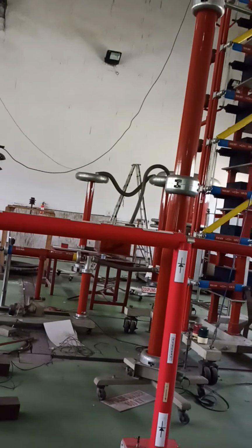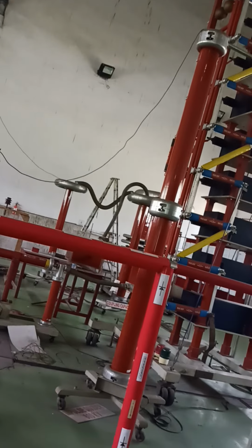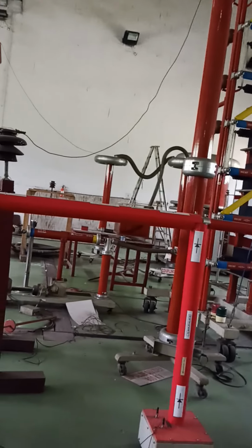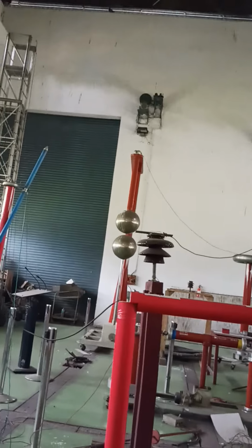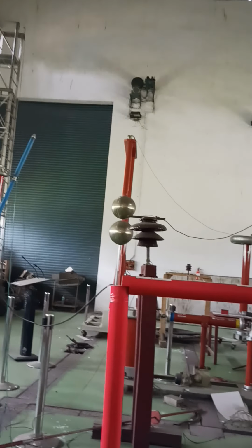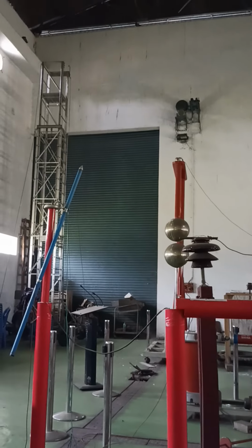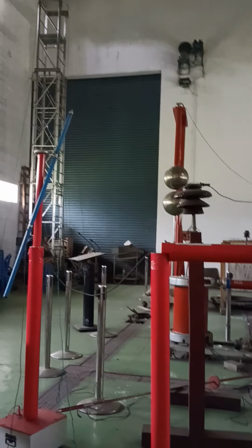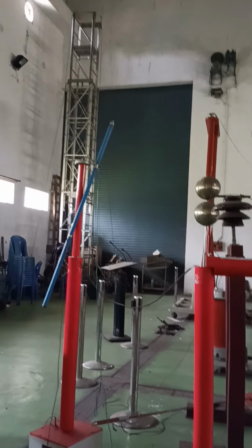Basically, we are applying the charges and testing how much insulation it has right now. The breakdown voltage we are testing. That means we apply a voltage there and check whether there is some charge discharge or not. It will be an 800 kV, 1.2 microsecond impulse. Oh, 1.25 microsecond. These are the characteristics of a normal thunderstorm.